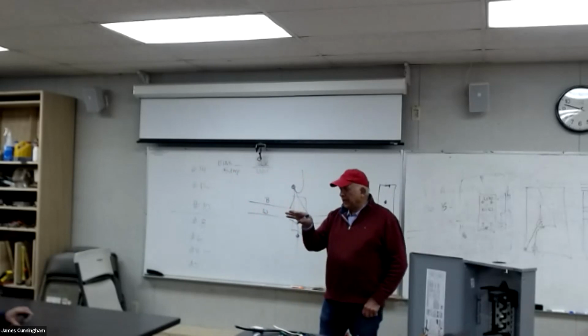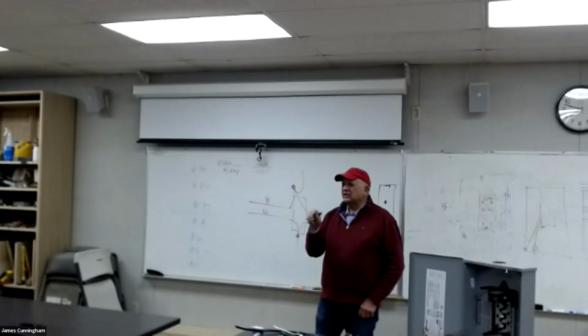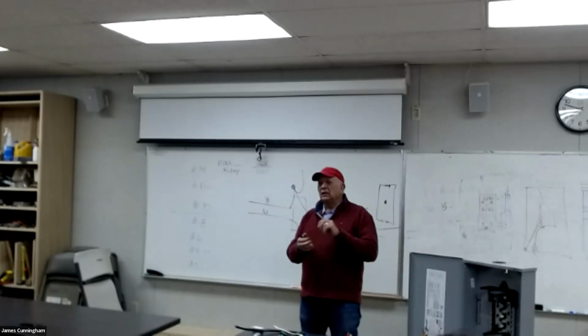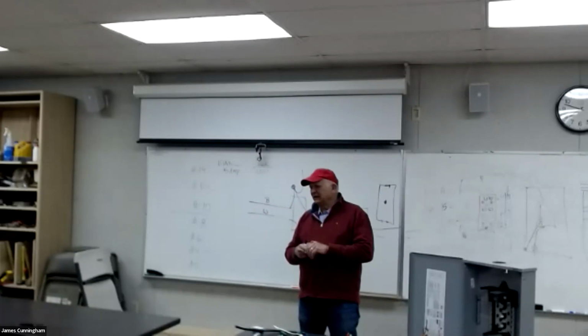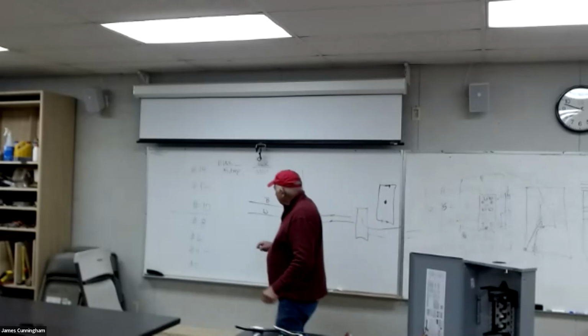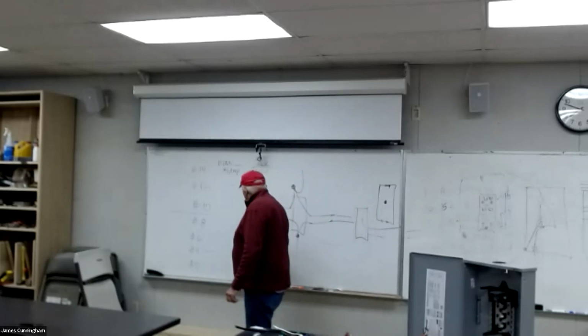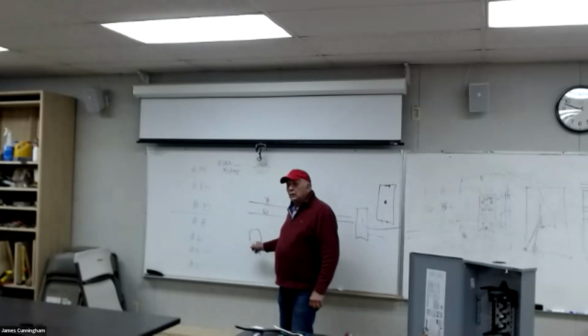Yeah, but remember now that we have to have a separate breaker for every room, every bedroom, every room, for the hallway. For the lights, it has to be on a separate circuit. So if I have a bedroom, I have to have 2 circuits. One for the plugs, one for the lights. You can't have the lights for the whole house on one breaker.